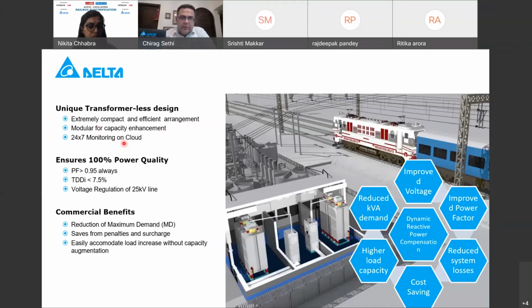Of course, the monitoring can be done 24/7 on a cloud-based platform. Our maintenance engineer, as well as the maintenance staff at the customer end at the TSS, can log into our web page at any time, or see on their mobile at any time the condition of the system, how much the harmonics are, and, in case of a breakdown, a fault log is maintained. This feature is provided in our solution. Of course, the basic requirements are power factor greater than 0.95, total demand distortion less than 7.5%, and voltage regulation of the feeder line. These are the main distinct performance parameters of our solution.